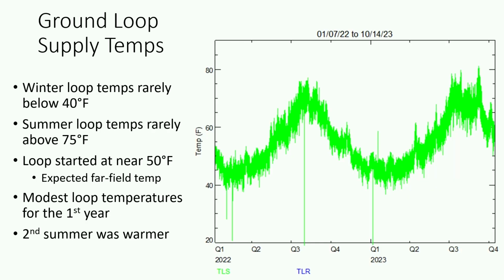Here's ground loop temperature. This does what every geothermal system did and what it was designed to do. The winter temperatures were rarely below 40. The summer temperatures were rarely above 75. The loop started at about 50 degrees, the far field temperature, but then quickly fell into this annual pattern. The first year is here, and you can see it got back to about the same spot. Temperatures were a little higher in the second summer, but still well within what we expected and what it was designed for. Jens would probably tell you it was designed for 30 to 90 degrees, and we're well within those bounds.